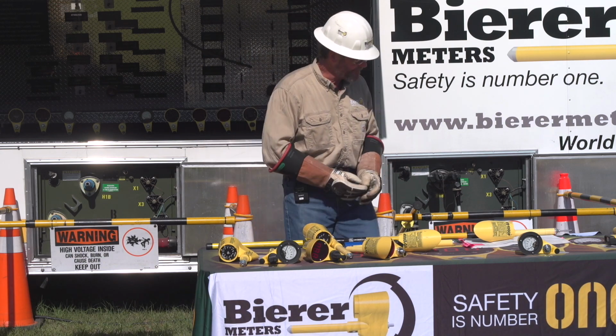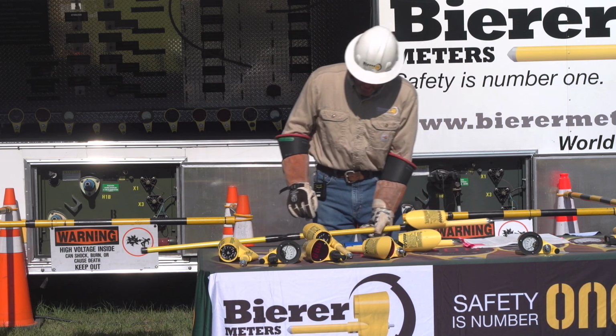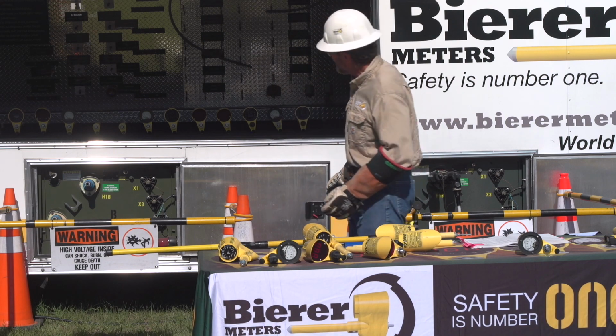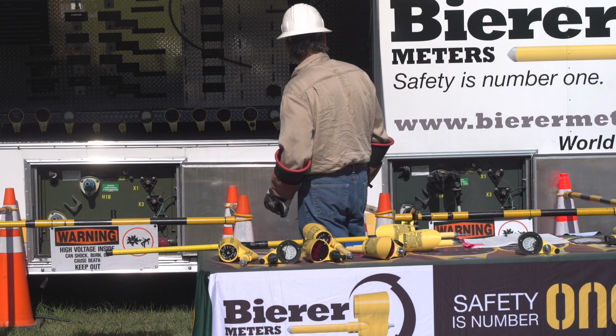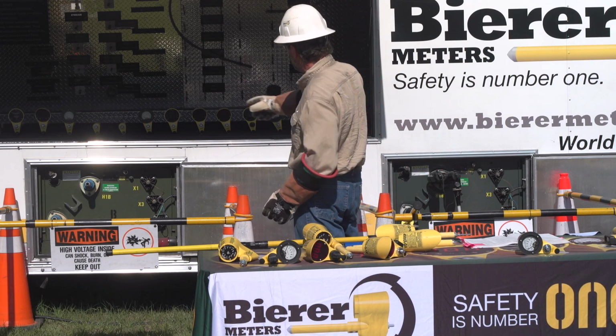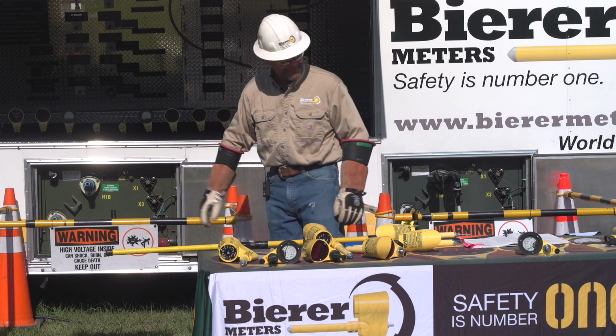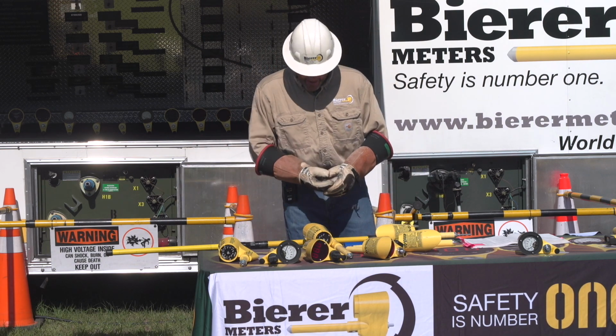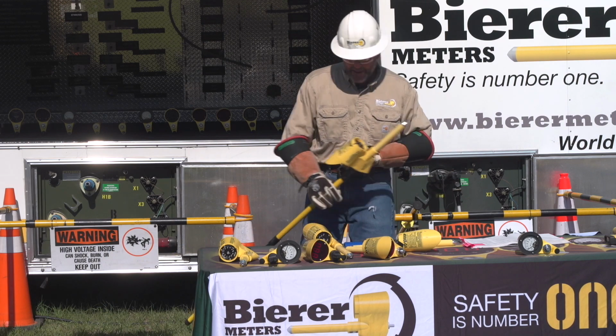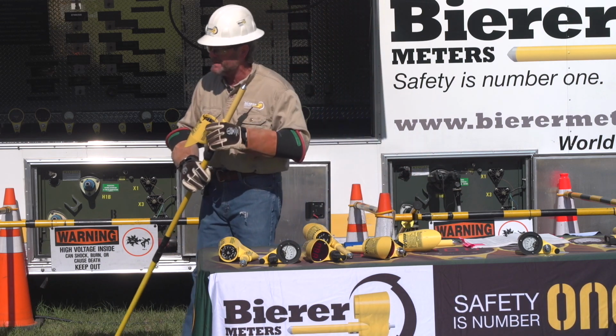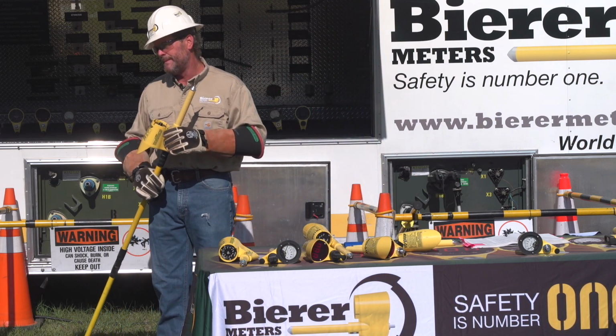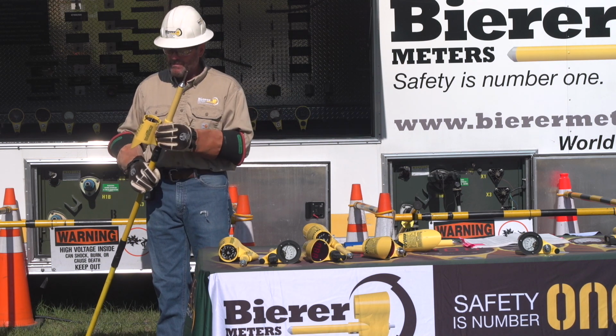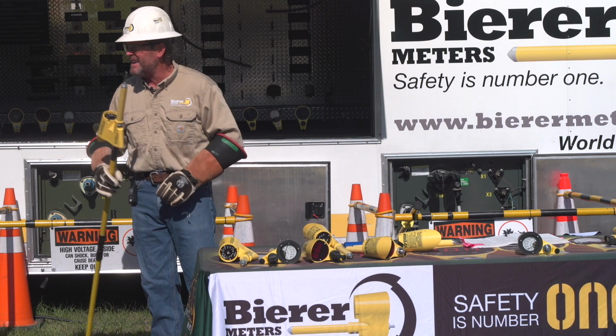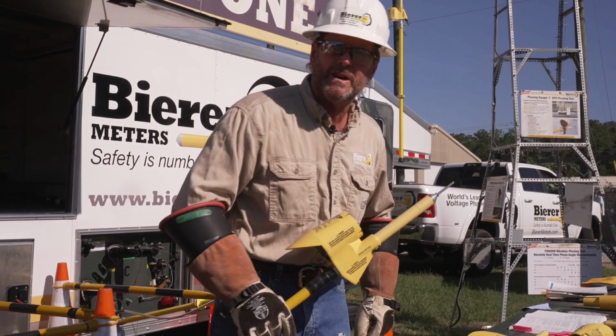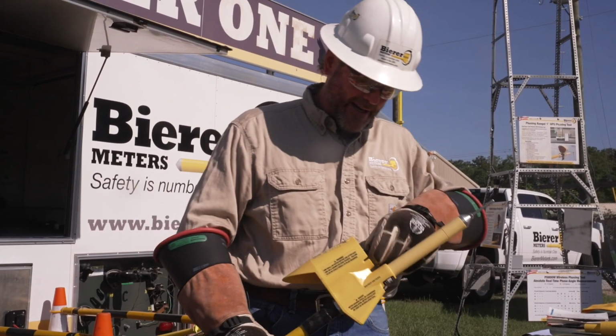So what we're going to do is go over some testing here. We're backfeeding these pad mounts, and we're going to go to capacitive test points and these hot bushings right here. This tool has a P setting, VD1000P, so it has a proximity setting. We could hang this tool out the line, hold it in our hand, and drive down the line in the truck, and find some bad spots here and there on the P setting.